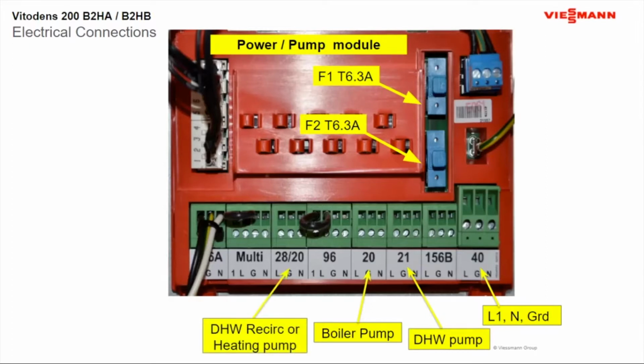Same with 2820 pump output. That can be, it's programmed to be a recirculation pump for your domestic side. So if you're doing any recirculation in the house, or say you've got a large house and they want to do recirculation, you can wire your pump right to here. You can go out and buy... you don't have to buy the expensive pumps with the push pins with the timers on it.